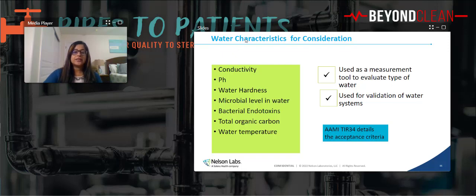AAMI TIR34 details the acceptance criteria for all of these measurements and gives good examples of how to measure them and what the quality system would look like. AAMI ST108, which is being revised from a TIR to a standard, goes into more detail about how you retrieve the water, what the sample should look like, what you can use to measure these, and provides an extensive write-up on how each level can be used as a measuring tool for your quality systems.